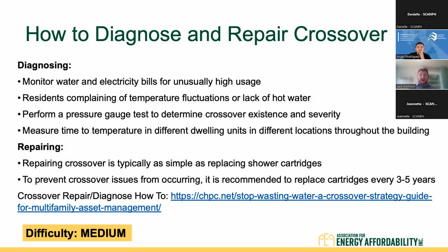If you ask a manufacturer who manufactures these shower cartridges, they say they should be replaced every 3 to 5 years. What would probably be a better approach for properties is to implement some of these testing strategies once in a while, maybe every few years. Every 3 to 5 years is probably a good cadence for measuring temperature throughout the building, and also doing a pressure gauge crossover test.